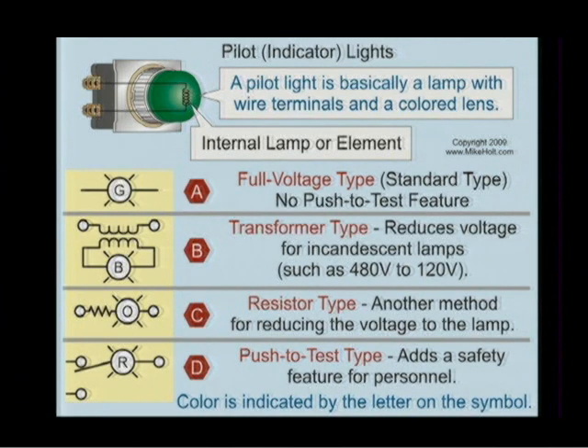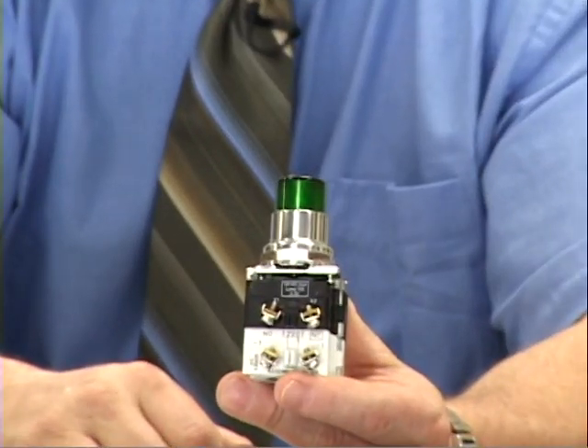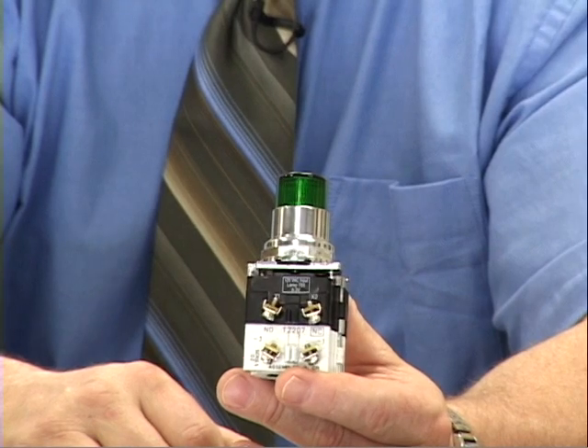Now, Dan, you told me about some experiences with the pilot lights you guys use, so I think it's a good time to talk about that. The pilot lights that we generally use have the transformer type, and the bulbs that a lot of the transformers use are 6.3 volt. Hold on. So you get a 120 volt circuit going to, is that the one right there? Yes, this is the one. All right, we'll see if you can zoom in. That's a 120 volt circuit, and there's a transformer built into that specific pilot light that drops that voltage from 120 to what?